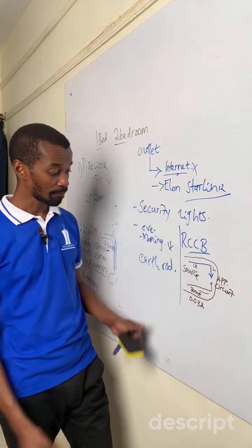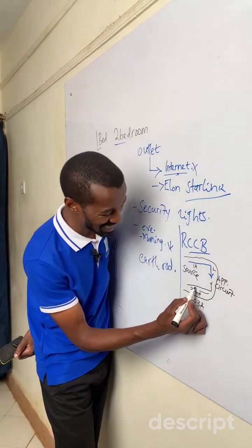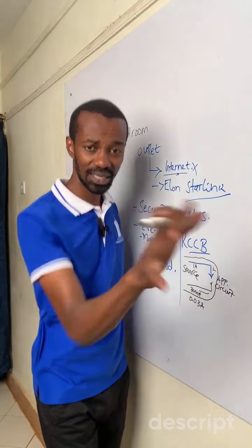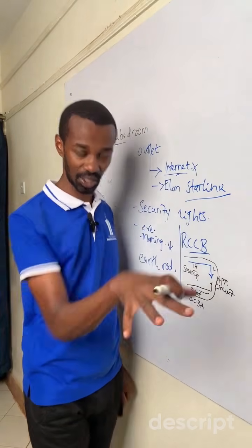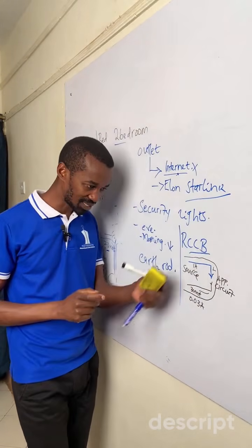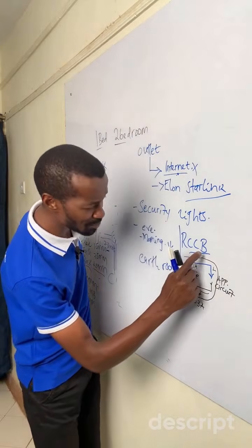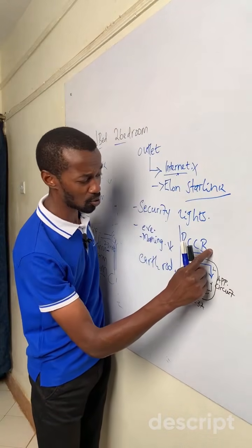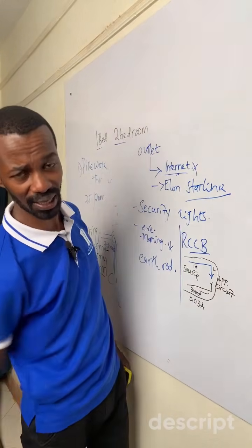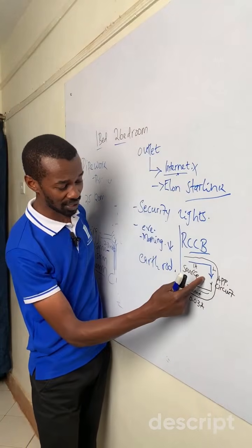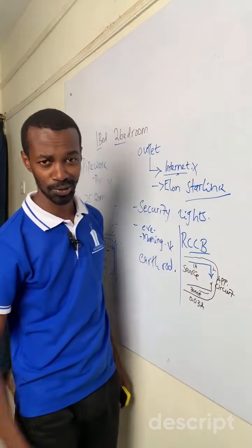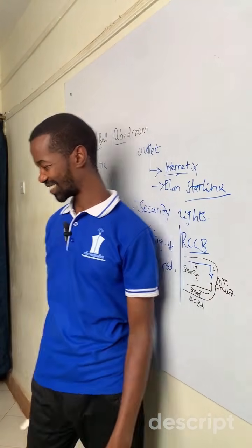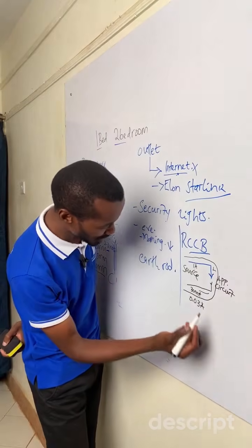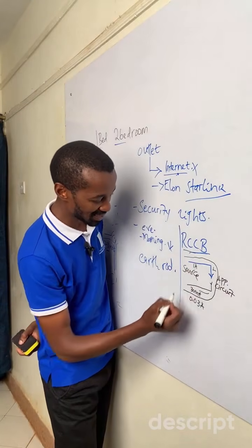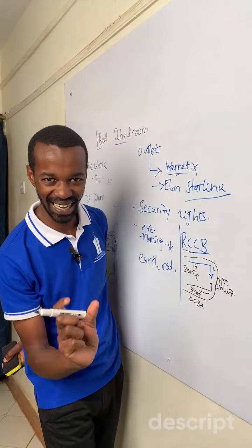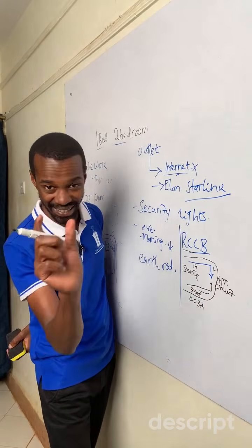Why will it trip? It will definitely trip because it has detected that something is leaving the circuit. The RCCB operates in such a way that if it detects that some energy has left it, it will shut down that circuit, protecting someone receiving an electric shock. So the main purpose of the RCCB is to detect any current that is leaving the circuit.